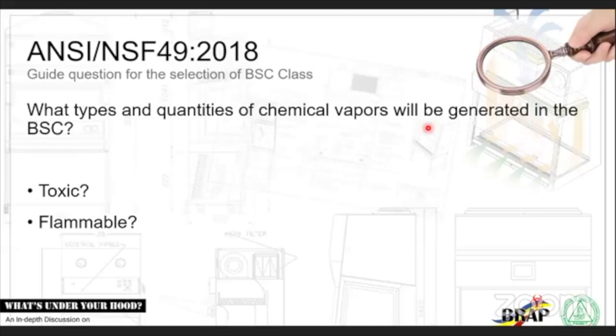Are your biosafety cabinets intrinsically safe to be used with flammables? So intrinsically safe means if there's a flammable chemical being used, will your biosafety cabinet not produce any sparks to ignite that vapor? Now, that's one of the things that you need to look at. If you're looking at a very minimal amount of vapors that could be easily diluted by the air, you do not need to worry. But if you're working, for example, with liters of absolute alcohol inside your biosafety cabinet, now you need to be worried. Di ba minsan nag-ground nga kayo sa static? So that's one of the things that you need to look at, the static energy. Are your sockets safe? Won't they produce sparks?